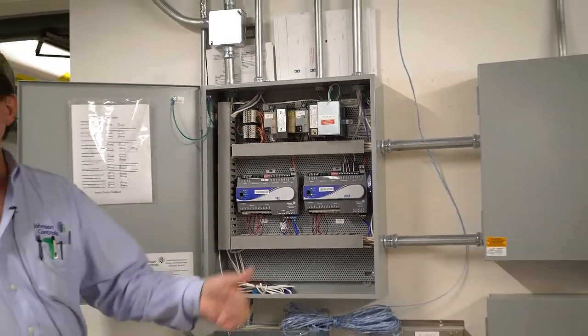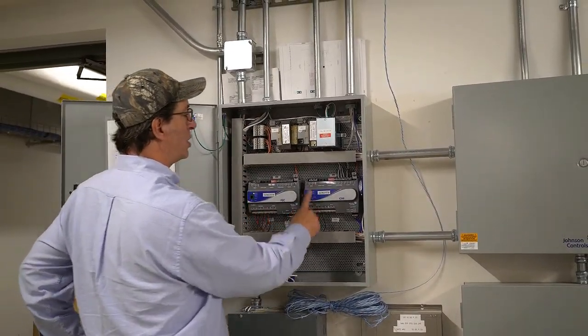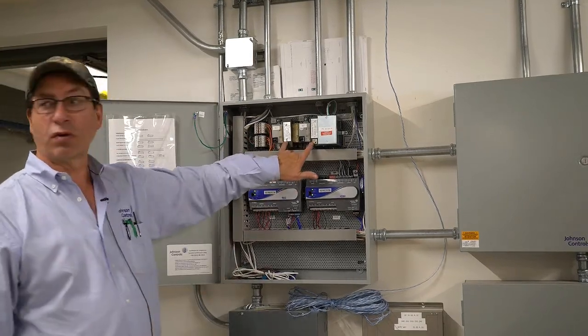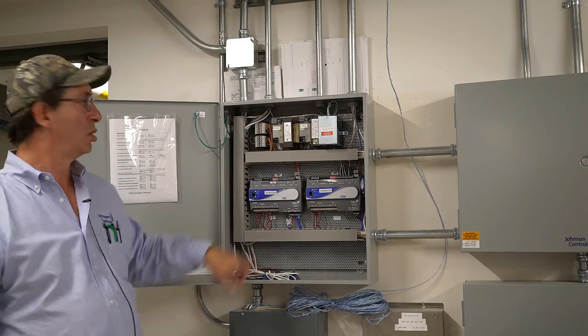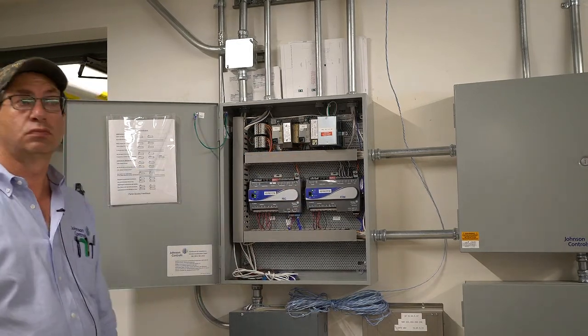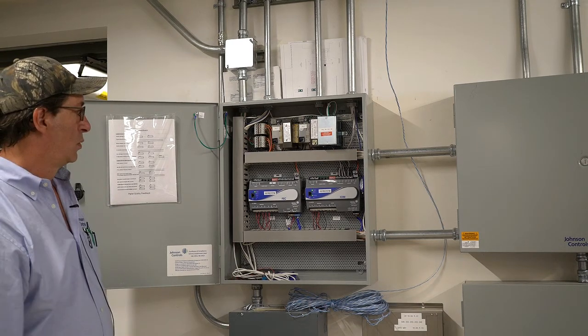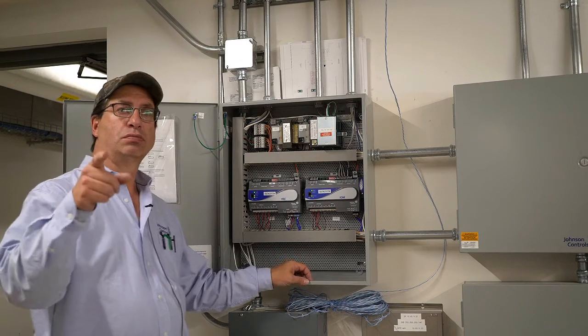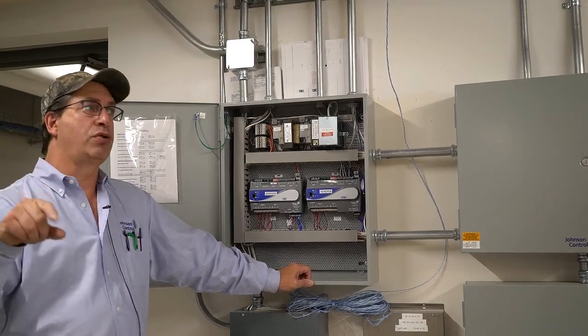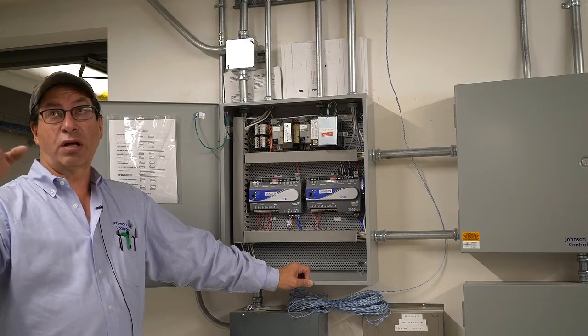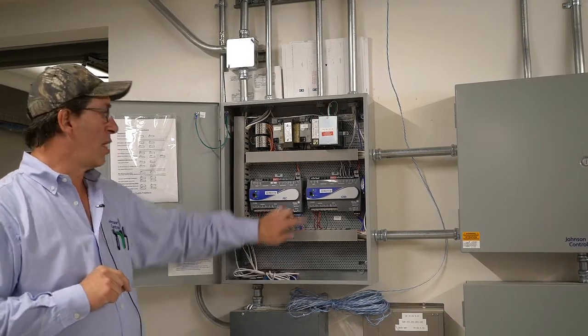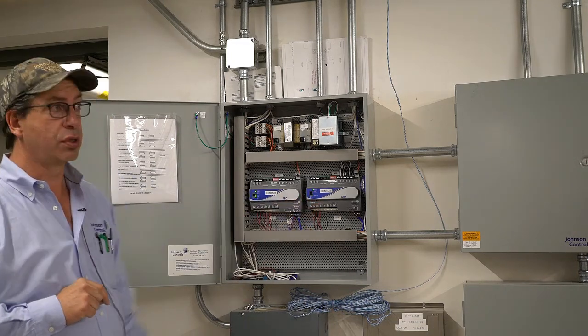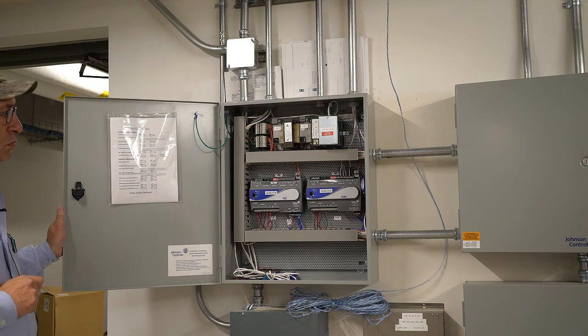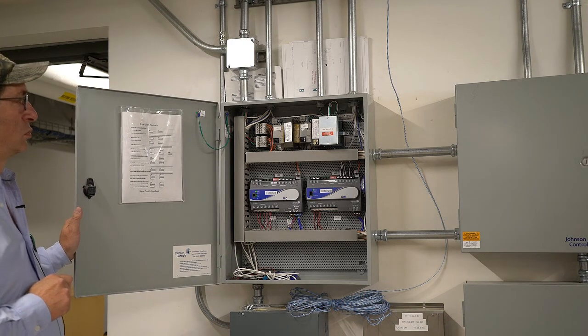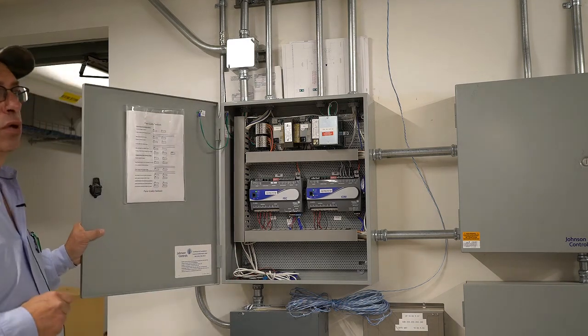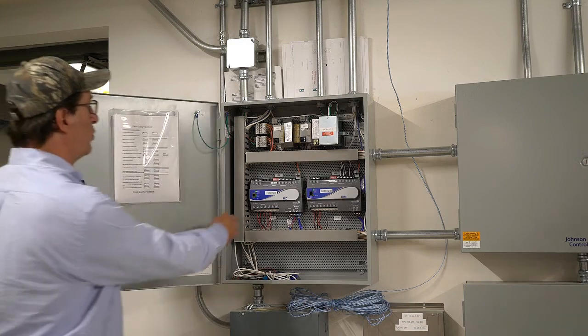Yep. So another thing, for troubleshooting purposes, if you come down here and these lights are on, if this one's dead, you'll notice there's two transformers here. We usually pull one off each transformer. Check these reset buttons. Okay? So all the sensors, so our temperature sensors that we have on the heat exchangers over here on the hot water system, all the signals going out to the steam valves, all come out of here, off this heating system controllers. So the outdoor temperature sensors come back to that also. Yes, I believe that's what we were looking at on the point schedule upstairs, yes. I believe it was input 1 right here.